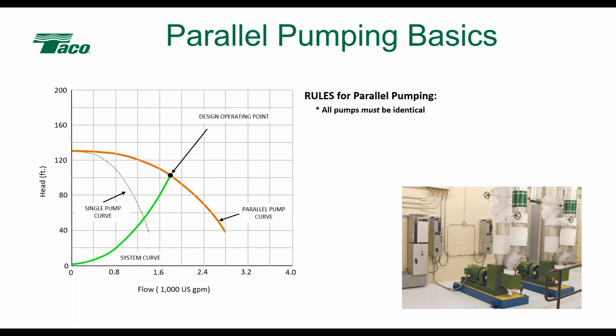And then Bill said, do you ever run over 60 hertz if you need more pump without exceeding FLA? That's a touchy one. Generally speaking, because of the way pumps work, and the way the casing and the impeller are designed as a system, we don't go over speed a whole lot. I've seen some pumps operate up to about 62 or 63 hertz, but that's about the upper limit we tend to go to. I always recommend that if you want to go above 60, contact the rep or factory. I don't care whose pump it is. I don't recommend it. I've had a couple of jobs where I had to go to 61 or 62 for a very narrow band of operation, but I don't recommend it on a regular basis.